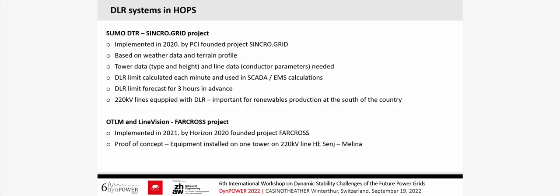Some details about the DTR limit: it is calculated every minute, and we have a forecast for the limits for 3 hours in advance. The result each minute is also used by EMS and the SCADA functions in the control room.